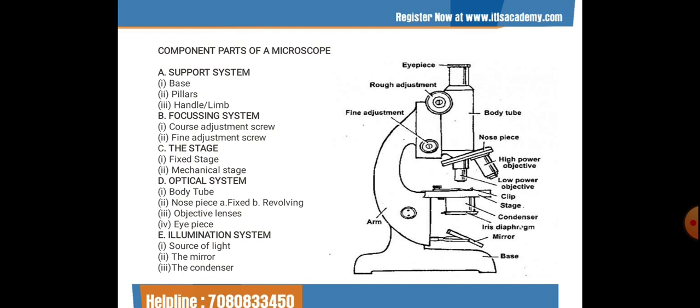The eyepiece houses a fixed diaphragm. It is at the plane of that fixed diaphragm that the image projected by the objective will be seen. On the shelf of the fixed diaphragm, the eyepiece can be fitted with a scale, markers, pointers or crosshairs that will be in simultaneous focus with the focused image. It also works in combination with the microscope objective to further magnify the intermediate image so that the specimen detail can be observed very clearly.